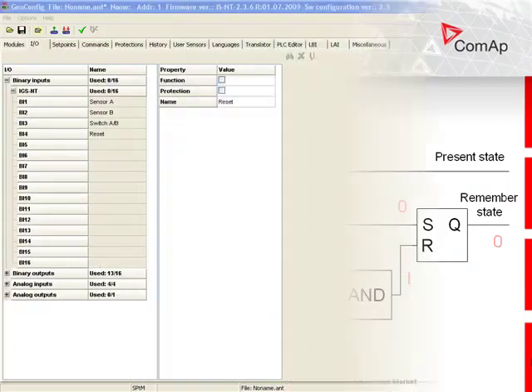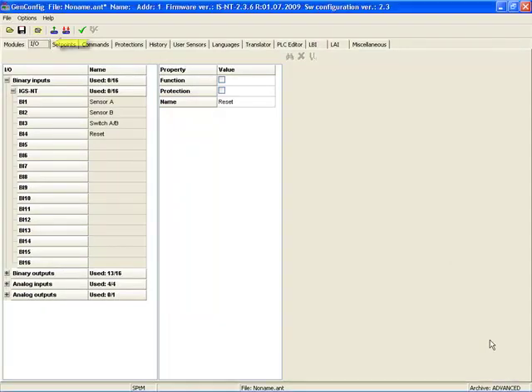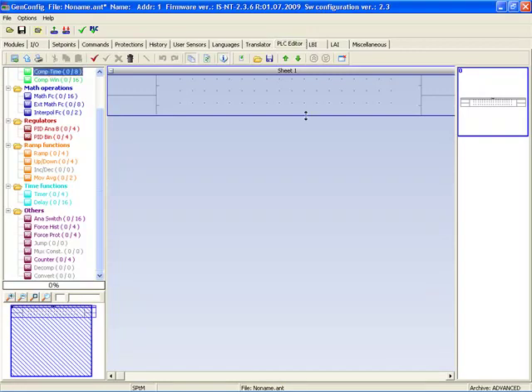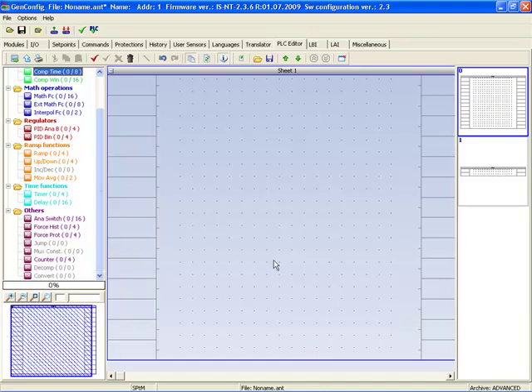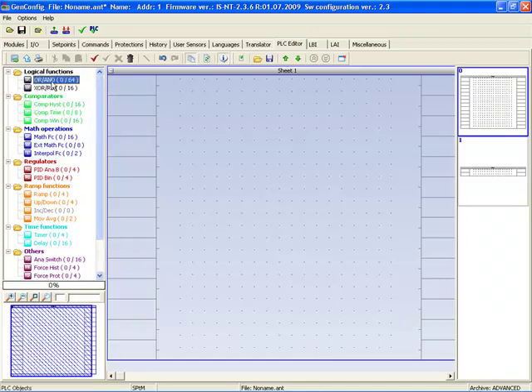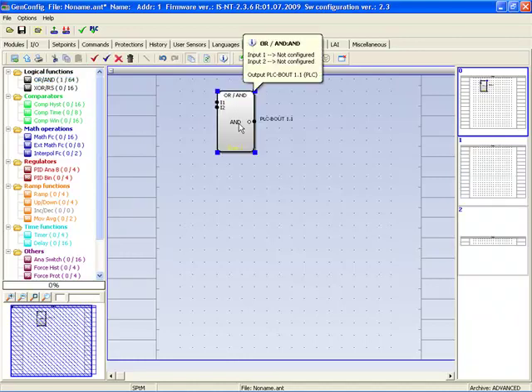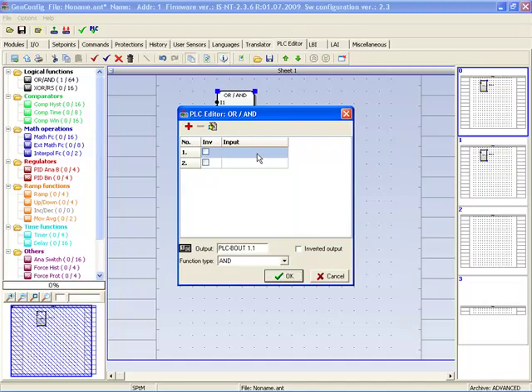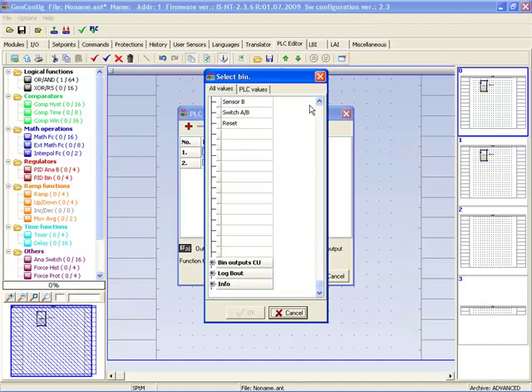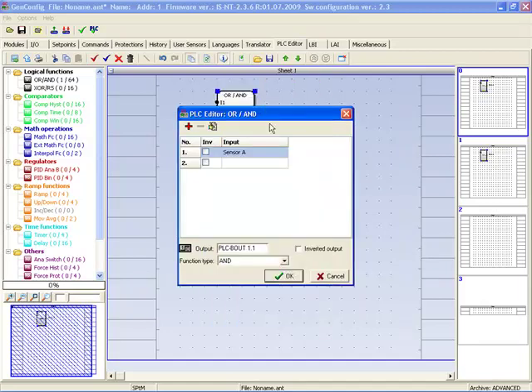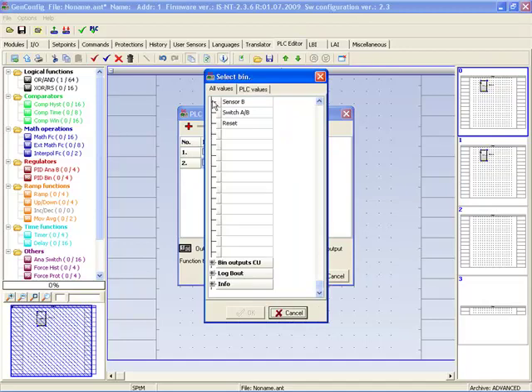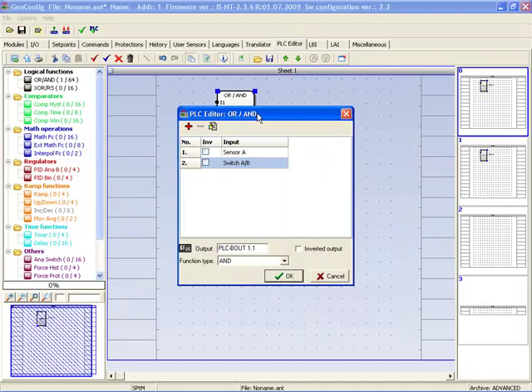Now I'll show you how to create this in GenConfig. In the card input and output, we define 4 binary inputs: sensor A, sensor B, switch AB, and reset. Then we switch to the PLC editor. In the PLC editor we add a function AND. In the AND function we define binary input 1 as the signal from sensor A and binary input 2 as the signal from switch AB. Set the function to AND and click OK.